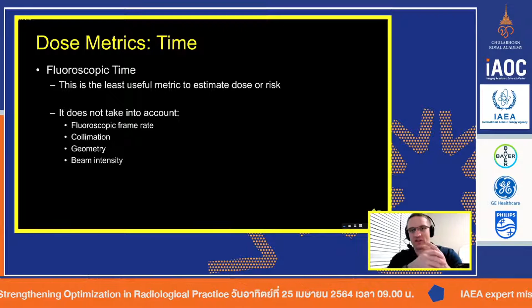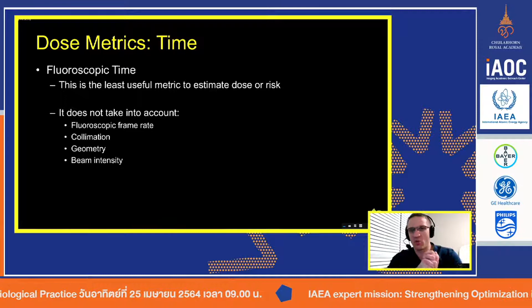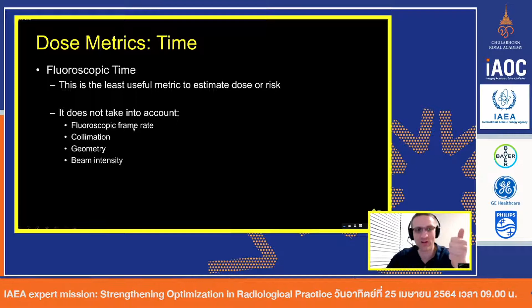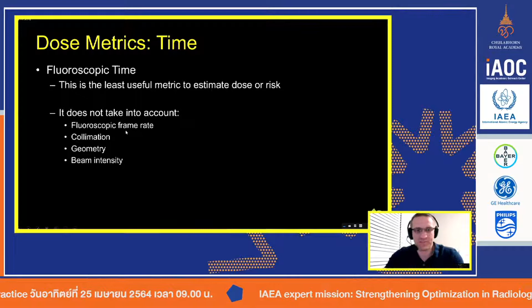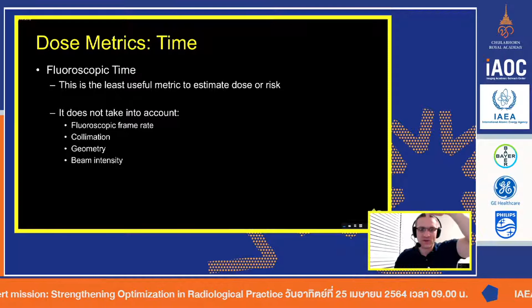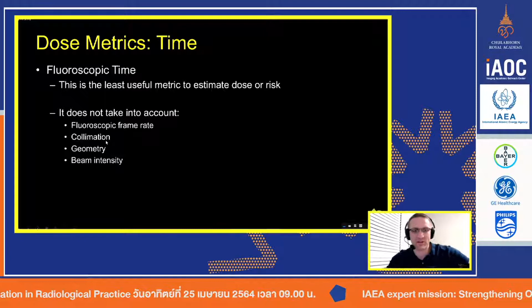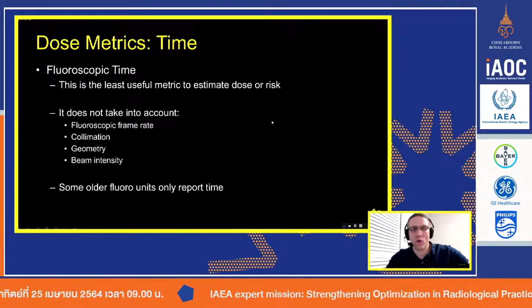Now, you may have sufficiently modern equipment, where all of your major centers and even your community centers don't have old 10, 15, 20-year-old equipment, in which case I would say don't even worry about collecting this. It's a metric that is difficult to use because it doesn't take into account frame rate. So if you're using 30 pulses per second versus 15 versus 7.5, the dose to the patients is so much different in each of those scenarios, but fluoroscopy time doesn't tell you that. It doesn't tell you if you were really well collimated or if the whole time you were fully open. It doesn't tell you the geometry, if you were doing everything laterally or obliquely versus anterior-posterior, which we know is going to be your lower dose because technically we tend to be thinner in that direct dimension, etc. It just doesn't take into account all of these things. So why would you collect it? Do it only if you must, especially for the older equipment.